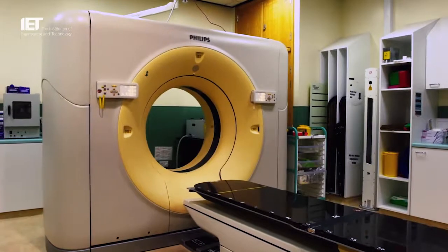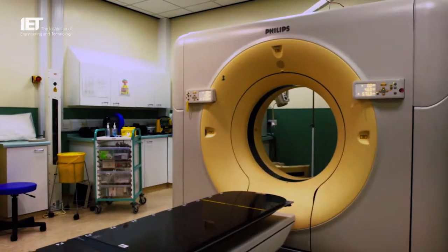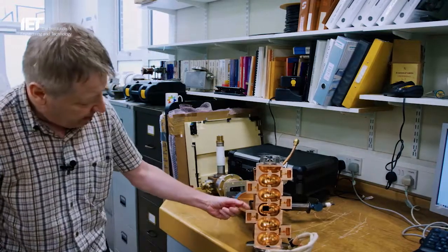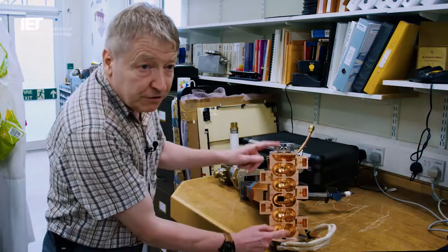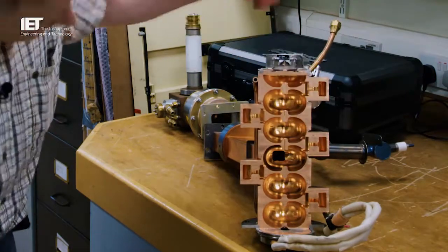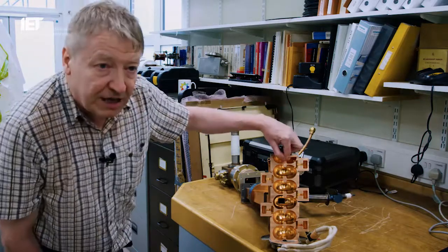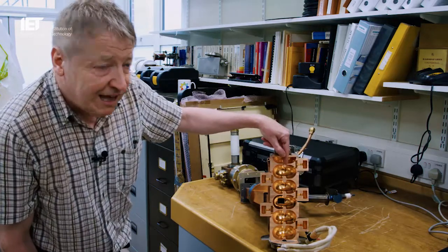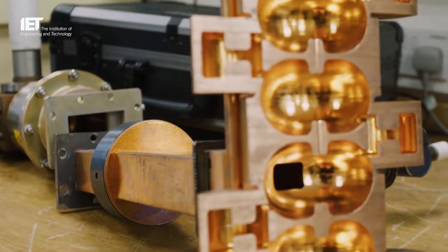tumour is. A LINAC, a linear accelerator that we use here, is the medical LINAC. It's a device which uses high energy radiation to treat cancers, so it's MV radiation. So this produces microwaves, and instead of going into the oven, they come along this part, they travel out here and they go up, bounce there and bounce backwards and forwards. So these are going positive, negative. The electrons get injected in, and when this goes positive, the electron gets accelerated. When that one goes negative, this one goes positive, gets accelerated again. Now the electron then hits the target, and these will give us 6 MV of X-rays that we want.